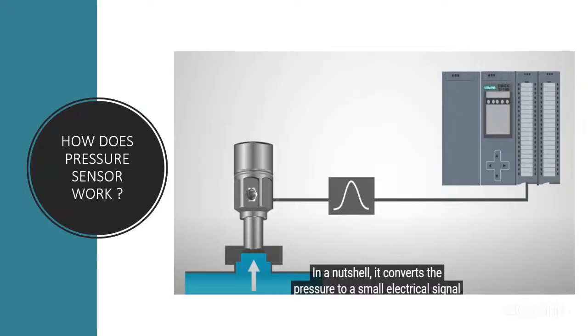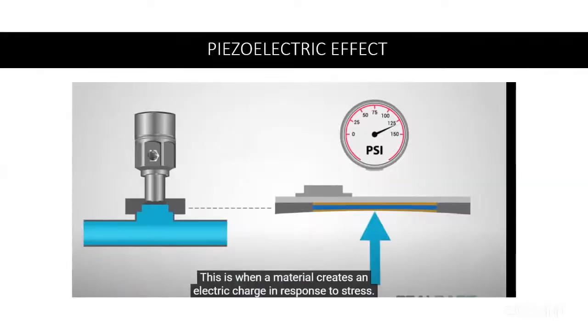Most pressure sensors function using the piezoelectric effect. And that takes us to the next slide. This is when a material creates electric charge in response to stress. The stress is usually pressure, in the case of a pressure sensor, but it can also be bending, twisting, or vibrations. The pressure sensor detects the pressure, and then it can determine the amount of pressure by measuring the amount of electric charge directly here.